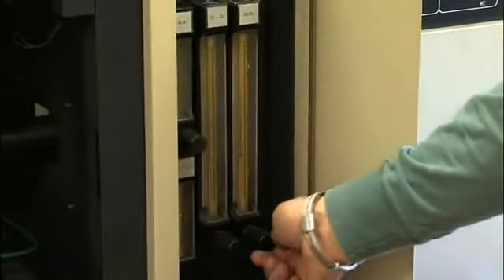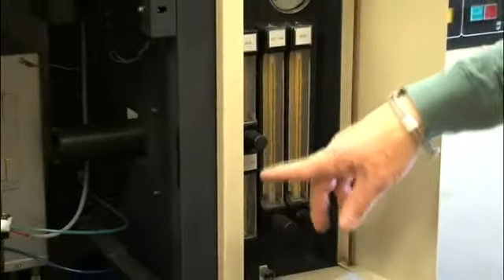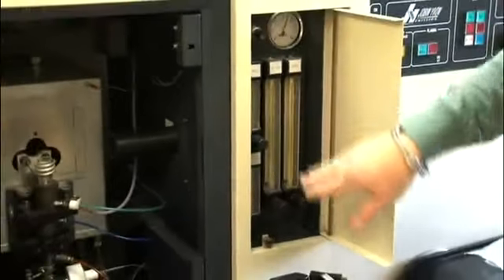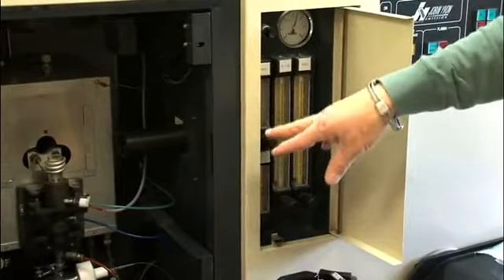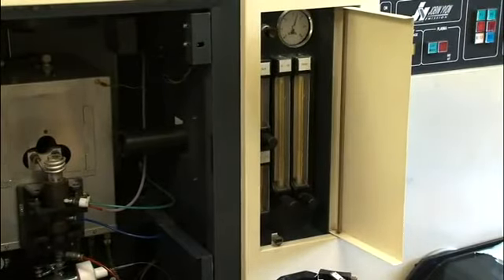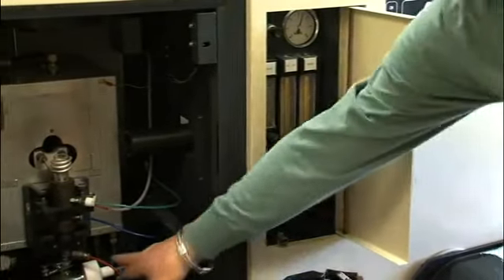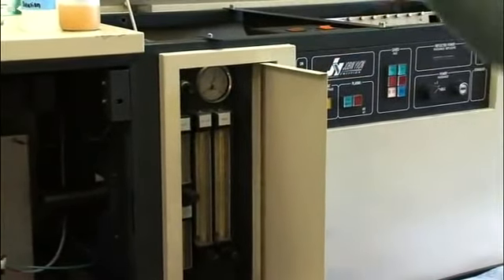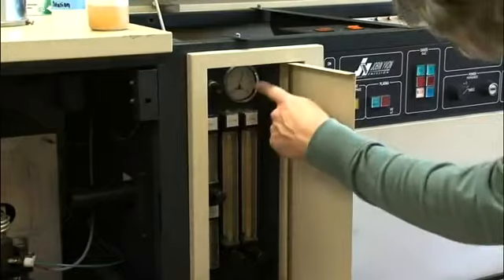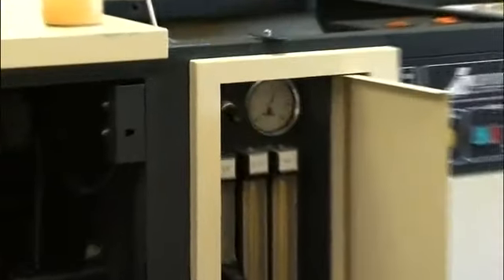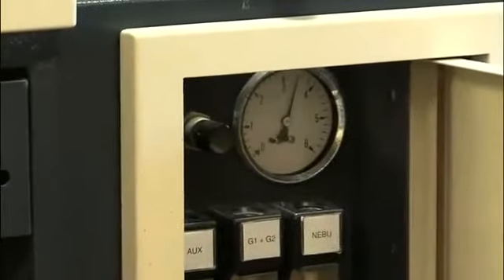I'll show you how to adjust the nebulizer pressure. This is the flow meter for the neb. It's left all the way open, and the flow is established by the nebulizer. The pressure for the nebulizer comes through a regulator. Your other gases are regulated by the pressure regulator on the tank. So your neb pressure, which is here, is cut down some from your 90 pounds that are coming in. So it's roughly about 3 bar, which comes out to be about 45 psi, I guess.